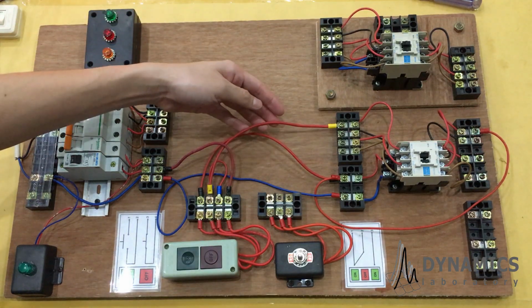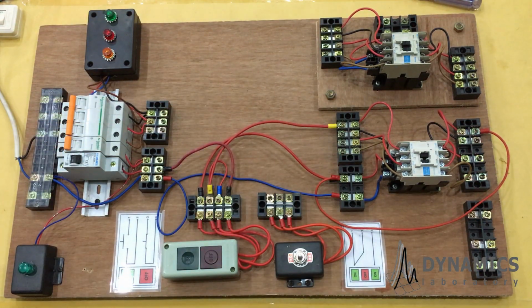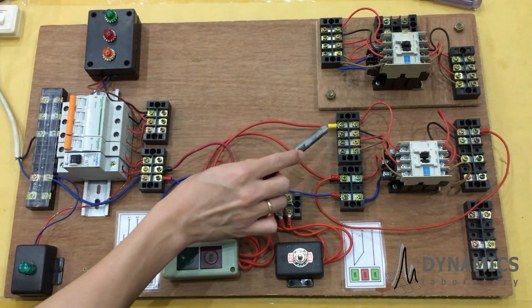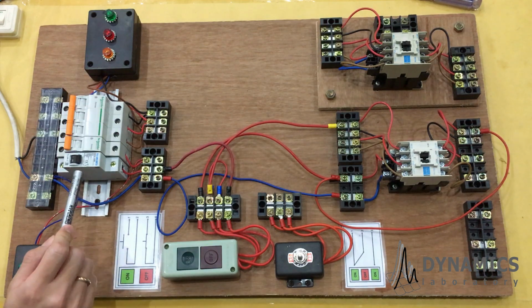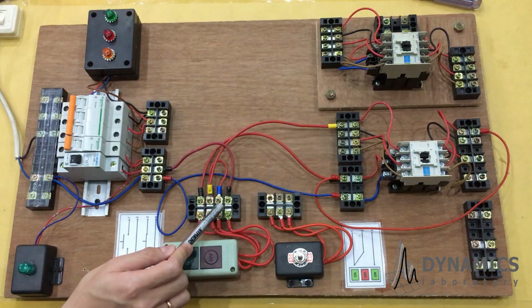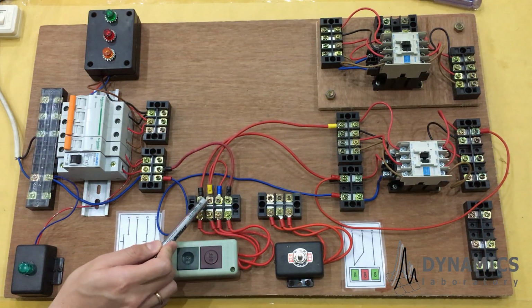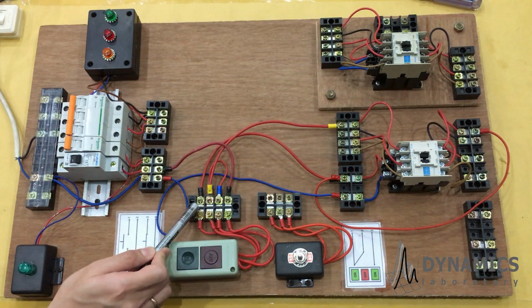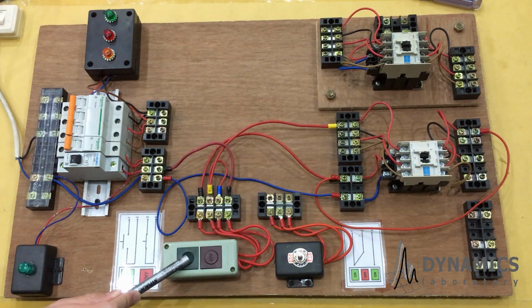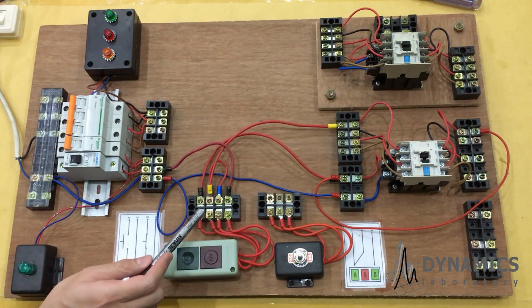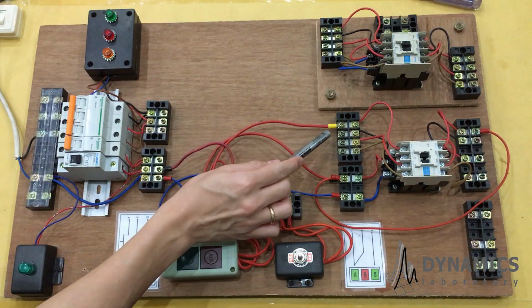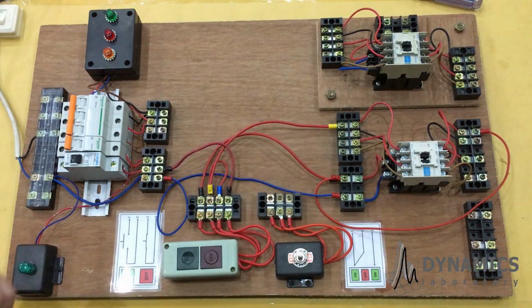Then we have to pay attention to terminal 13 and terminal 14. You see, when I release the on button, then the closed circuit is not formed. But the current will flow through terminal 13 and terminal 14. Take a look over here. From the control circuit breaker to leg number 4, leg number 3, leg number 2, but it doesn't go to leg number 1 because I don't press the on button in here. That's why leg number 2 and leg number 1 is not a closed circuit. That's why the current will flow to terminal 13, terminal 14, and come back to the coil contactor.